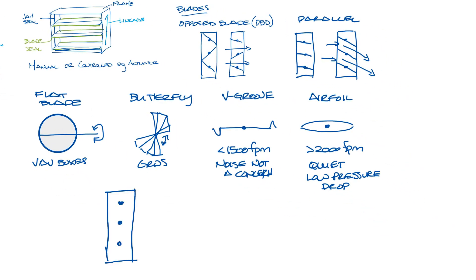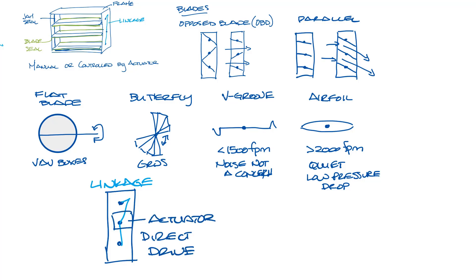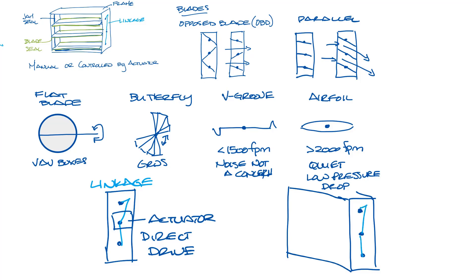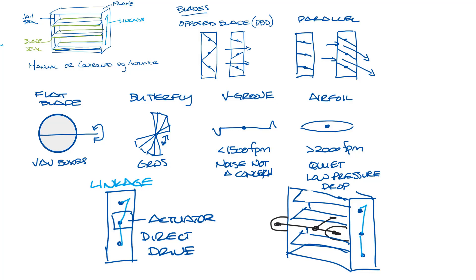The linkage connects the blades together. They're at the end of the damper frame and are driven by operating a single blade called the drive blade. You could mount the actuator right on the drive blade and now it's direct drive. You can also have what is called a jack shaft, which is offset from the damper itself. The jack shaft would connect to that blade and you would control it from the jack shaft, not directly from the end of the blade. In this case you would mount the actuator on the jack shaft to control the blades. This is commonly used when you have multiple sections of a damper connected together or when you want to internally mount the actuator.